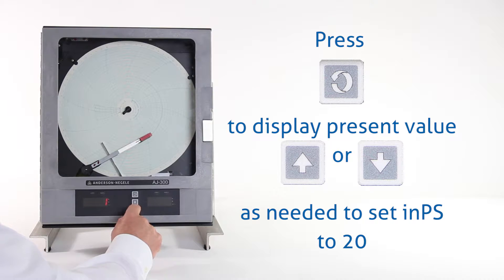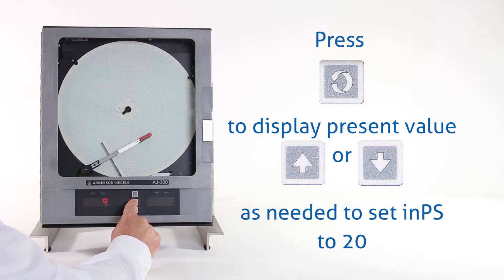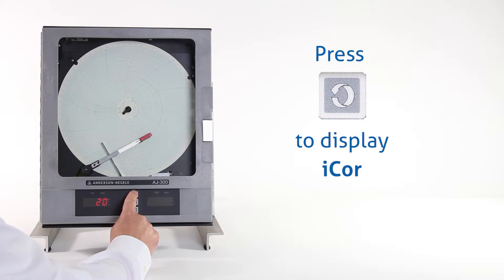For Celsius, this needs to be set to 20 for RTD input. So we're going to hit the up arrow key to get to 20. Once we have 20, we hit the scroll key.